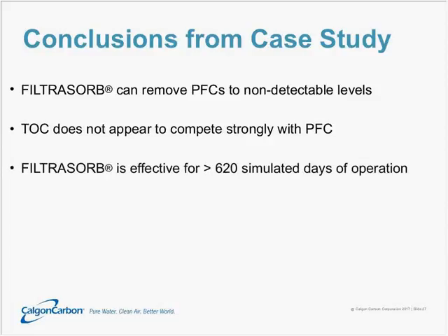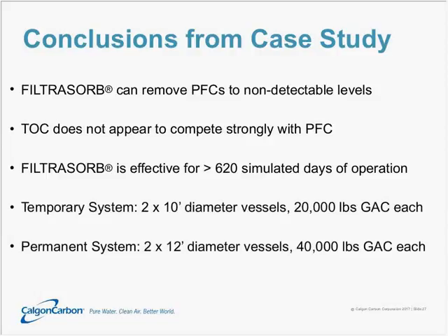A few conclusions from this case study: Filtrasorb can remove PFCs to non-detectable levels below 2 nanograms per liter. TOC does not compete very strongly with PFCs even at concentrations several hundred times higher, breaking through significantly sooner. Filtrasorb was effective for more than 620 simulated days with no breakthrough, never reaching the 70 PPT health advisory. As a result, the client installed two 10-foot diameter vessels with 20,000 pounds of GAC each as a temporary solution — placed online in March 2016 — and by December 2016, went ahead with a permanent system of two 12-foot diameter vessels each containing 40,000 pounds of GAC. The temporary system had zero detection of PFCs in its effluent throughout its entire duration.